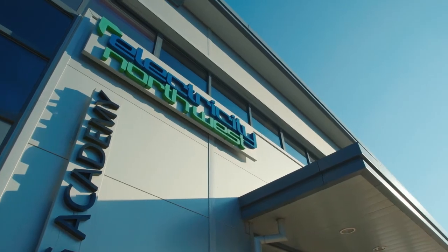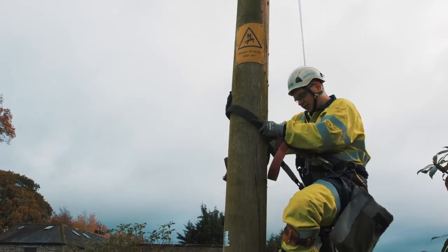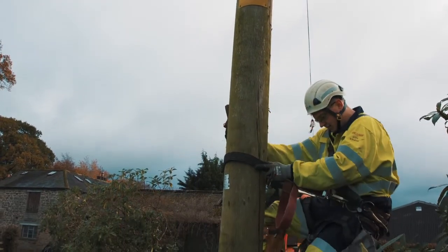Unfortunately, after a period of time, problems were identified with voltage drift on a large number of the Sentinel devices. What we've identified is that the voltages have been drifting up or down. Basically, we found that due to the environments in which these devices are installed, we've had to deploy additional environmental protection within cable connections and additional earthing kits as well. With these solutions in place, we have now been back to upgrade a total of 30 units, and we are happy to say that these solutions have worked successfully, and we're now into a period of upgrading the remaining of the initial installed 110 units.